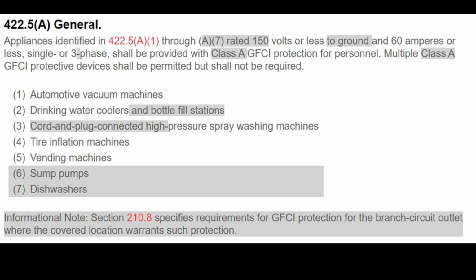All right, appliances identified in 422.5(A)(1) through (A)(7), rated 150 volts to ground or less and 60 amps or less, single or three-phase, shall now have a Class A GFCI. And as we discussed, a Class A GFCI is for protection of personnel, right? And that has a threshold of 4 to 6 milliamps versus a Class B GFCI for equipment that has a threshold of, I believe, up to 35 milliamps. Don't quote me on that one. I'm going off memory. But there's a large difference in that threshold.